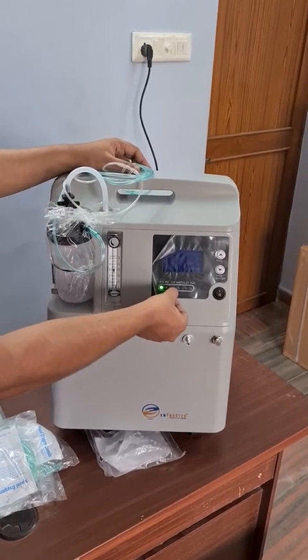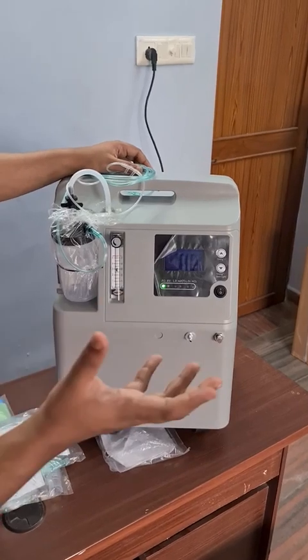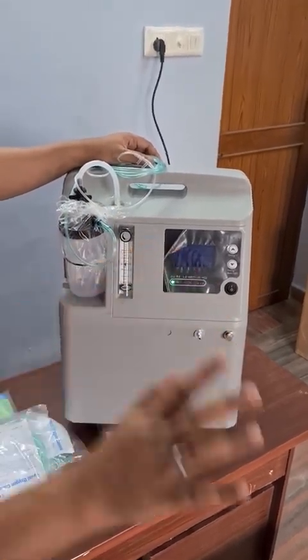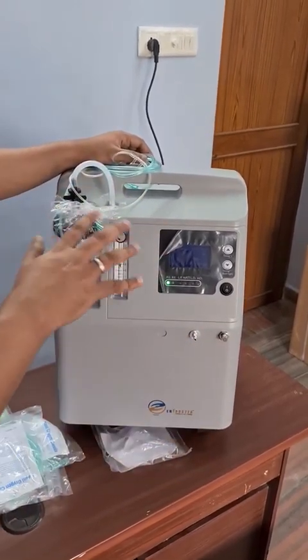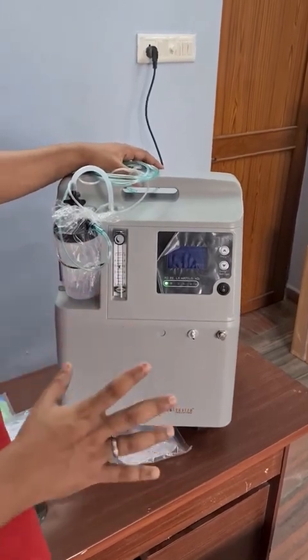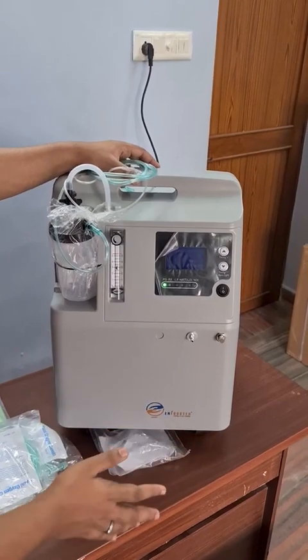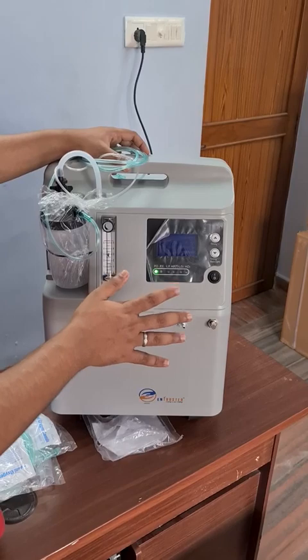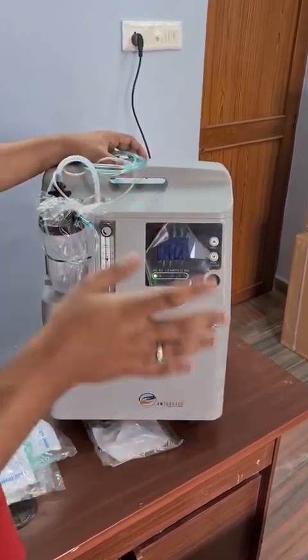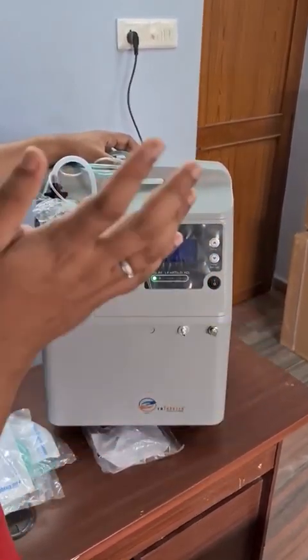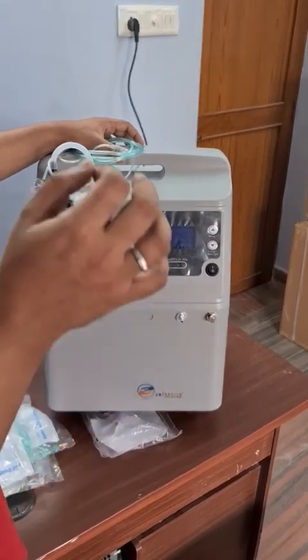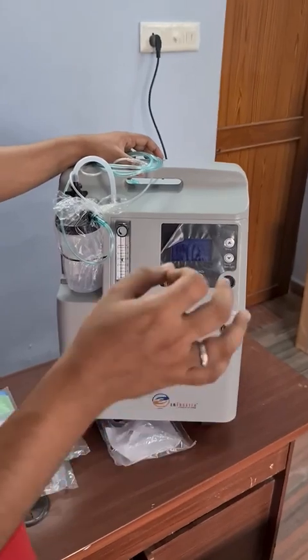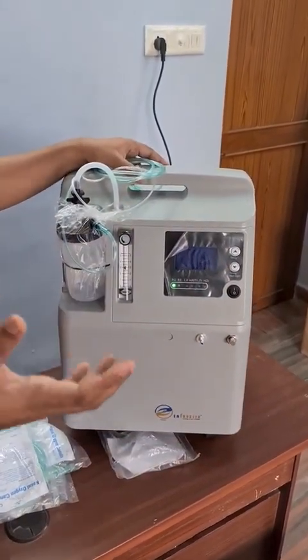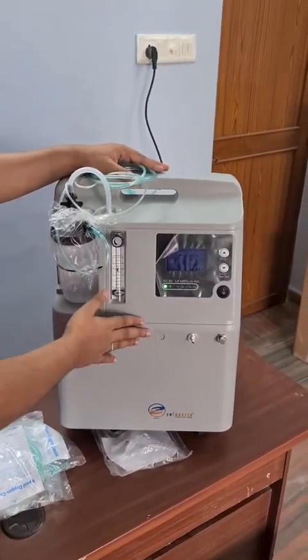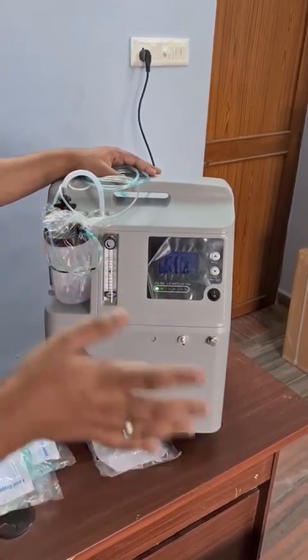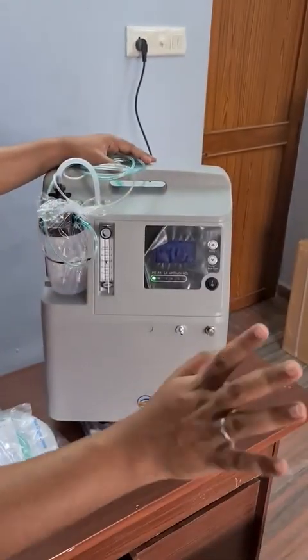Now coming on to the third alarm, this is low pressure, and the fourth alarm is high pressure. Low pressure or high pressure happens to the compressor when there are voltage fluctuations. So that is what I was telling you in the beginning of the video also. Compared to all the other medical equipment, the concentrator is the only device which requires a very precise and proper voltage. Since it has almost a 350 watts compressor inside, we have to always make sure the voltage entering the device is constant. And if you find the voltage is an issue at your location, you need to get a medical grade stabilizer, or at least a stabilizer which has 1.5 kVA output capacity and which is going to limit the upper voltage at 230 volts. If you get a normal stabilizer which we use for a TV or fridge, that will not work with the oxygen concentrators. So whenever this low pressure or high pressure light comes, make sure that the voltage in your place is proper, or try to source a stabilizer or give us a call.